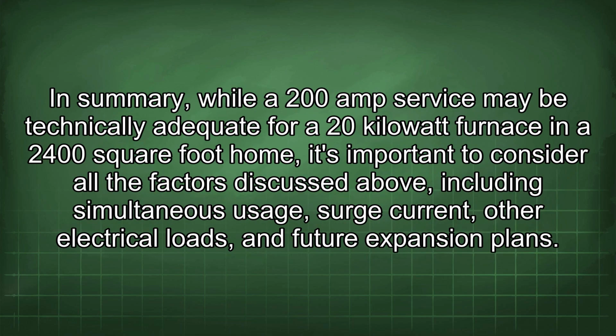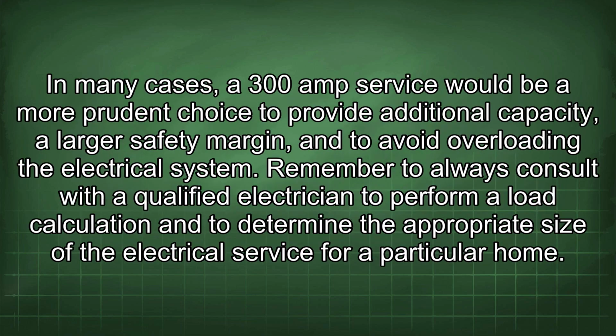In summary, while a 200 amp service may be technically adequate for a 20 kilowatt furnace in a 2,400 square foot home, it's important to consider all the factors discussed above, including simultaneous usage, surge current, other electrical loads, and future expansion plans. In many cases, a 300 amp service would be a more prudent choice to provide additional capacity, a larger safety margin, and to avoid overloading the electrical system. Remember to always consult with a qualified electrician to perform a load calculation and to determine the appropriate size of the electrical service for a particular home.